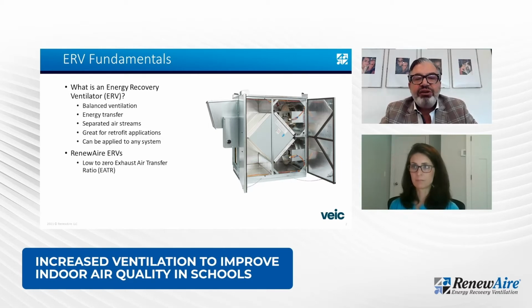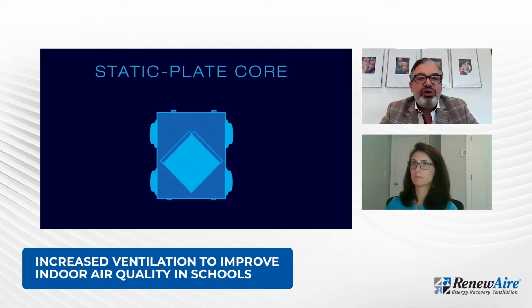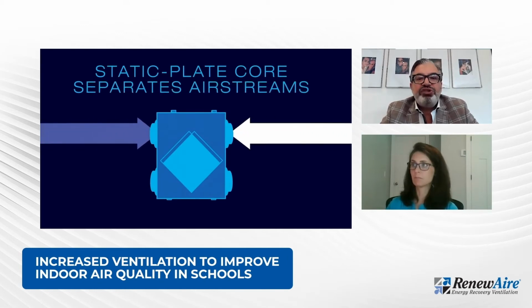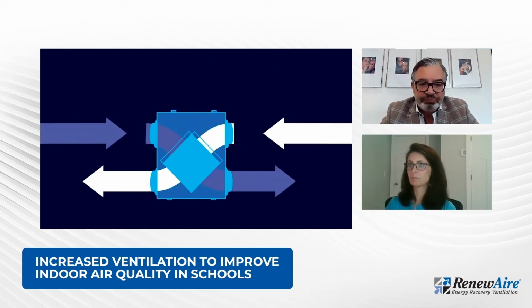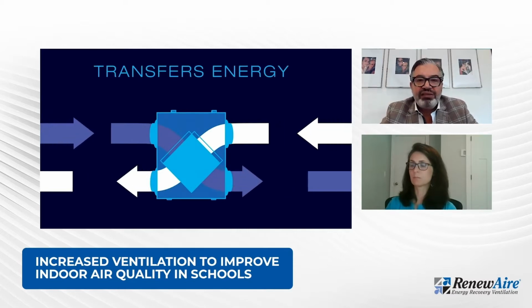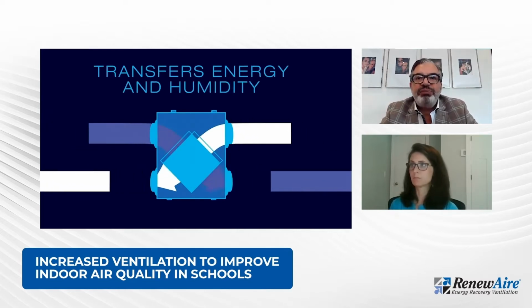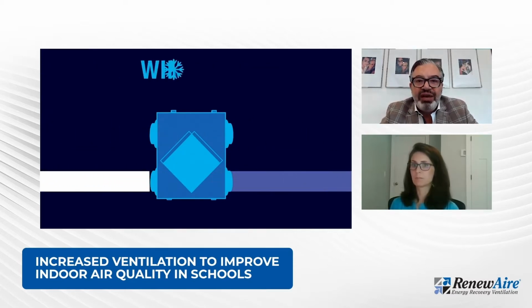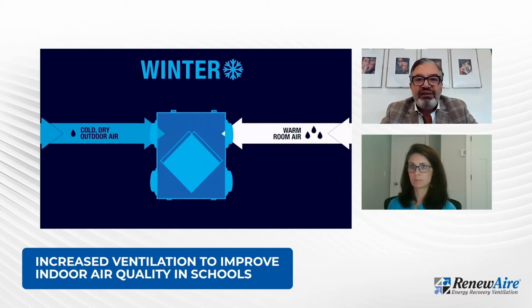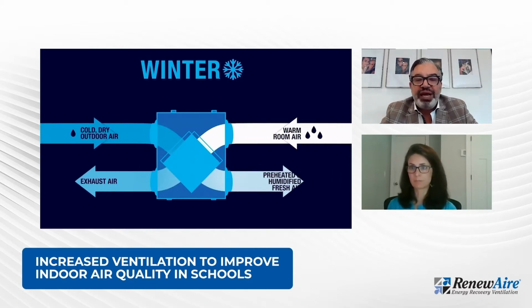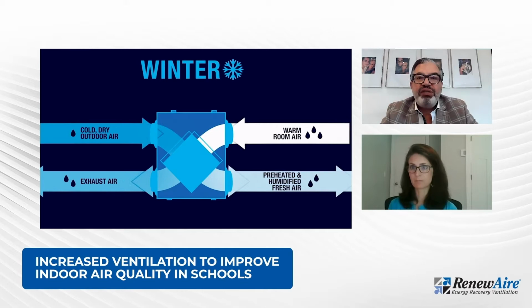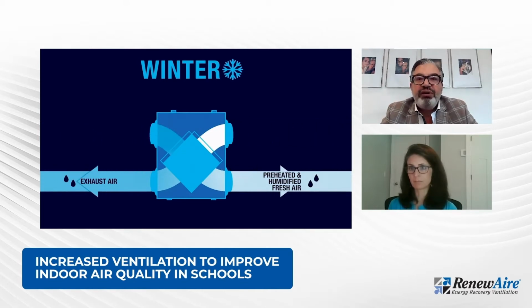So let's take a look at energy recovery and what that means, because there are various types of energy recovery equipment and they're not all the same. With Renew Air energy recovery ventilation, we have something called balanced ventilation. What balanced ventilation means is that when we take 1 cubic foot of stale indoor air and throw it out, we bring 1 cubic foot of clean, fresh outdoor air in.